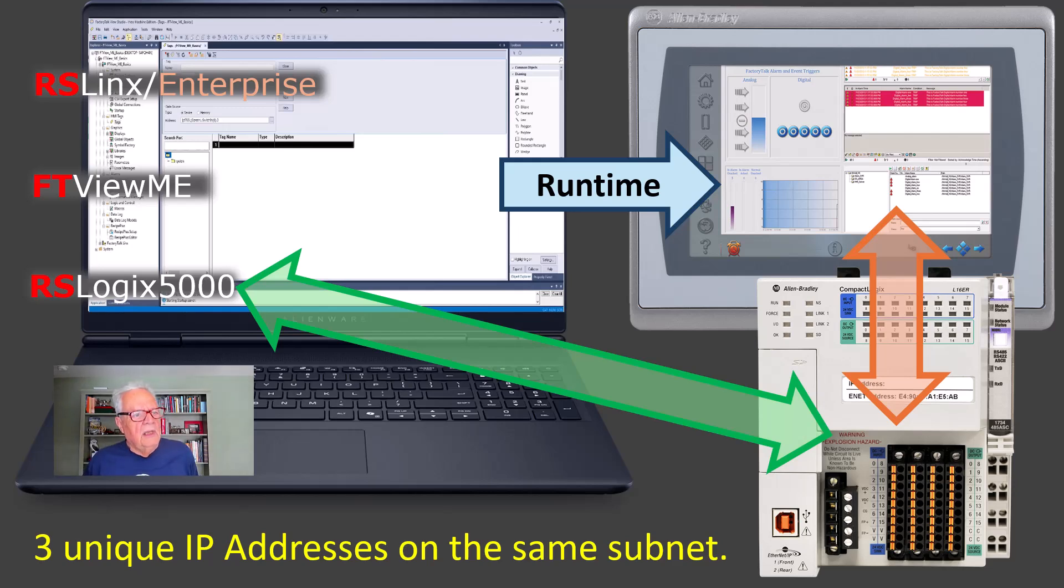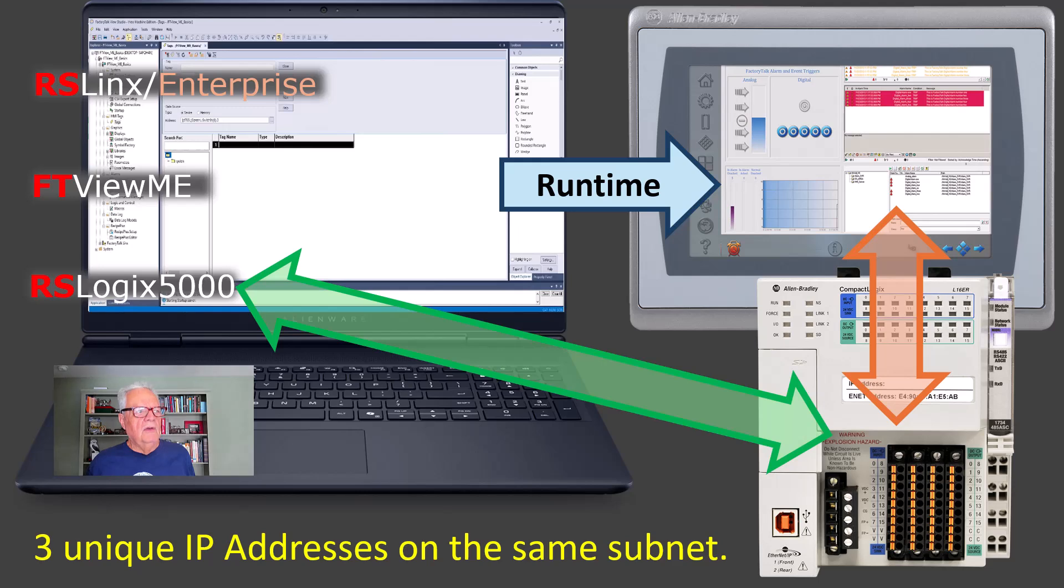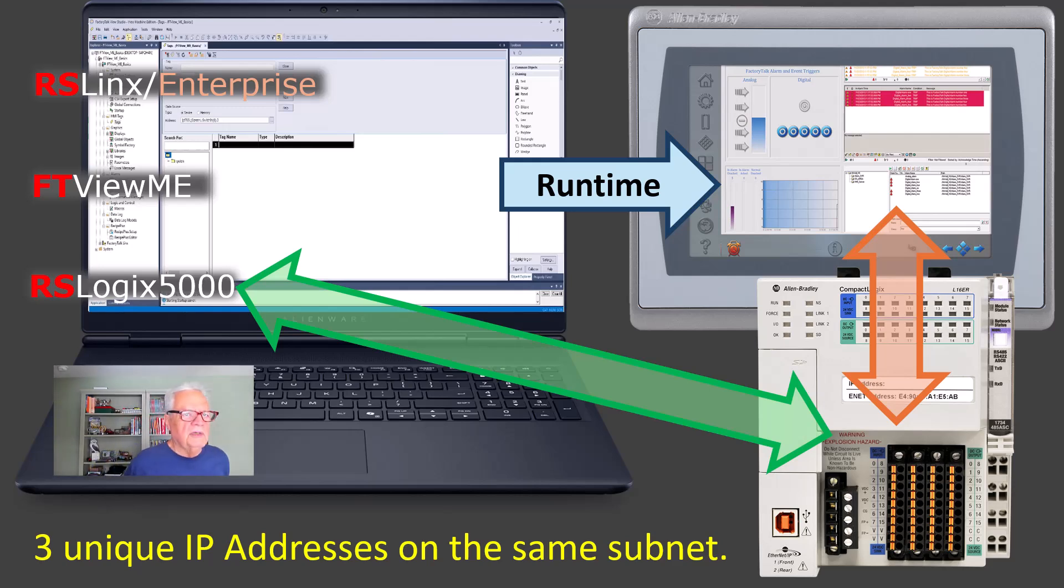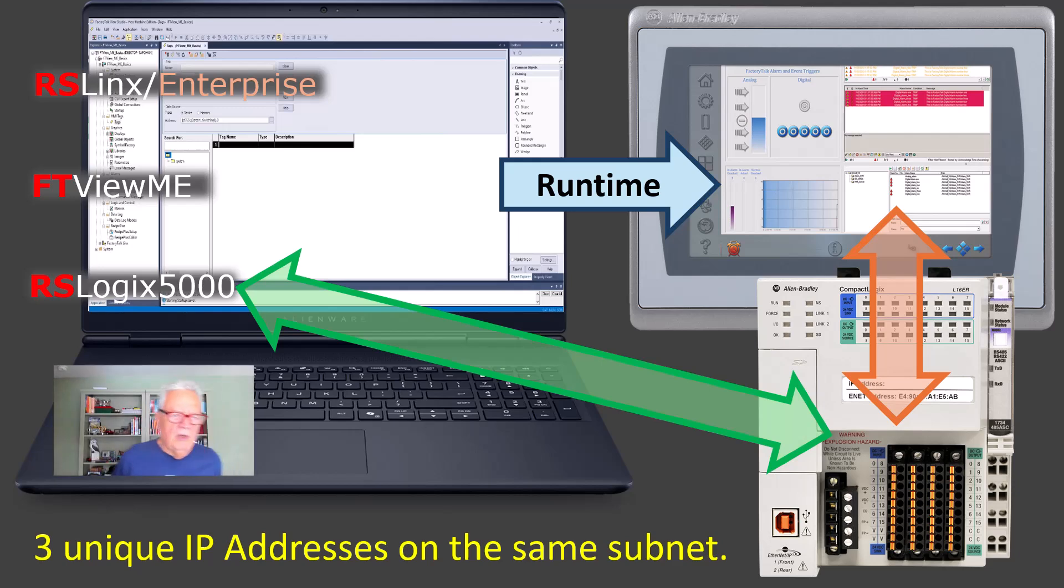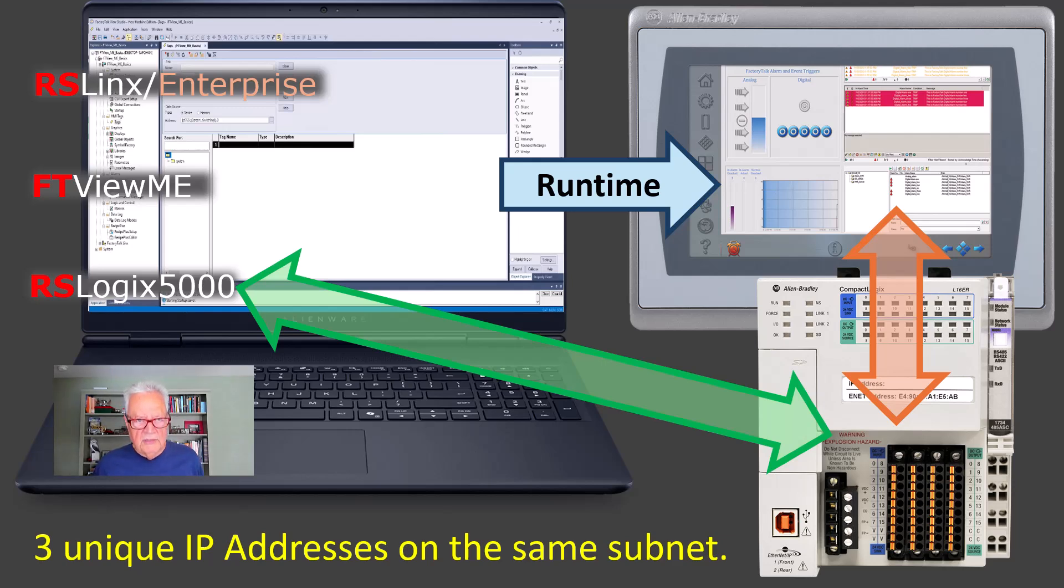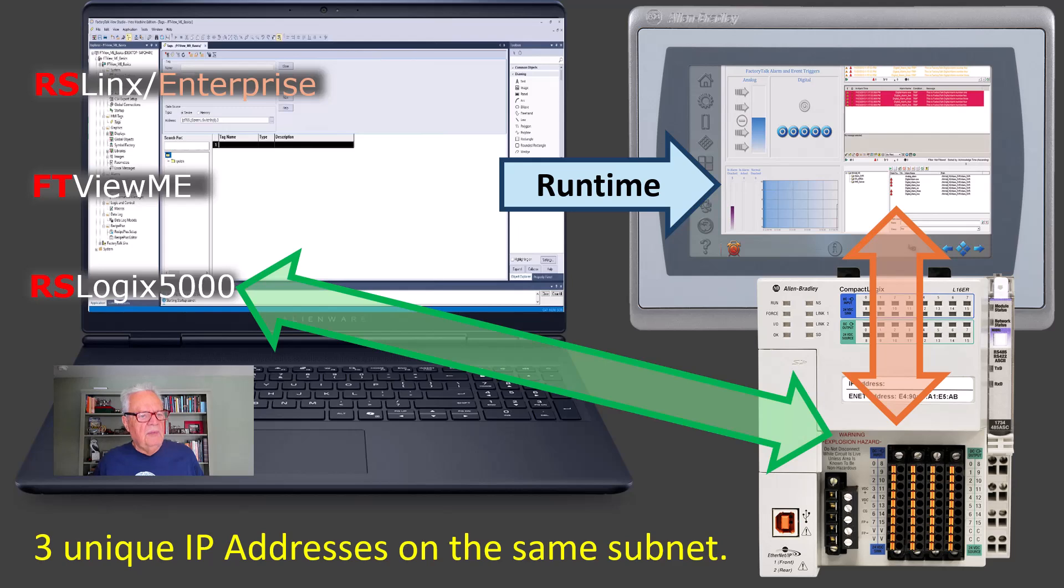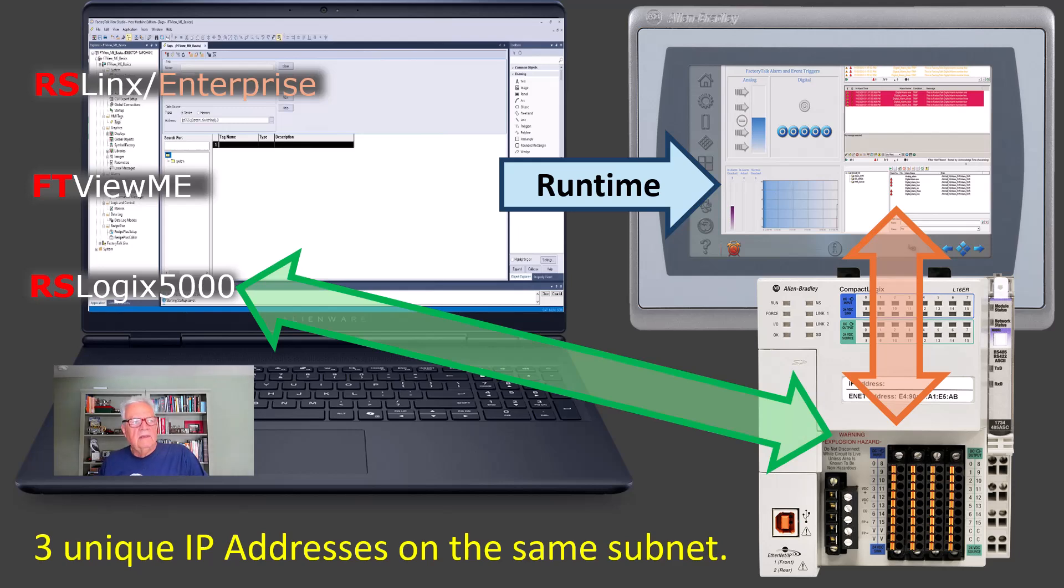Initially, it's already set up between 5000 and the controller to upload download to the controller, but you need to download the runtime to the Panel View. That is another driver, so to speak, that you have to set up, and then once you download the runtime to the Panel View plus, and you want to launch it independent of the laptop, then you need the additional communication that you set up between the IP address of the Panel View plus, and the Compact Logix controller, designated by double arrow. You have three unique IP addresses. This is typically the format, the environment, the data scape for a proprietary HMI.